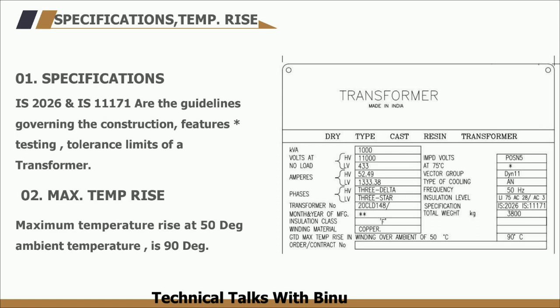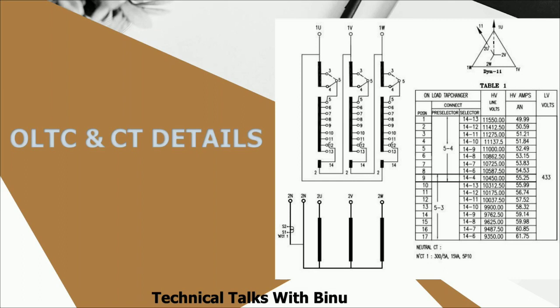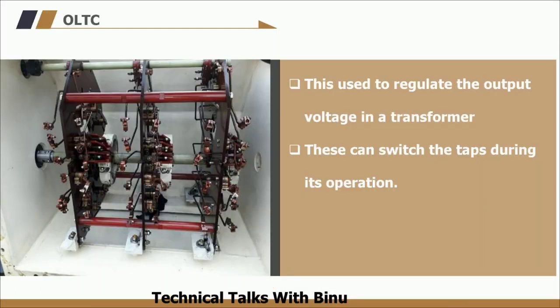It is also noted that the weight of the transformer is 3800 kg. Next is OLTC — On-Load Tap Changer. OLTC is capable of switching the tap position to provide voltage regulation while carrying the load. This OLTC has 17 taps ranging from +5% to -15% in steps of 1.25%. Tappings are taken from the middle of the delta winding. A separate video on OLTC operation and general arrangement will be done.